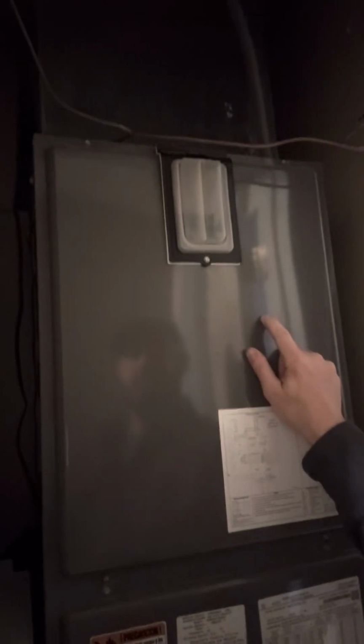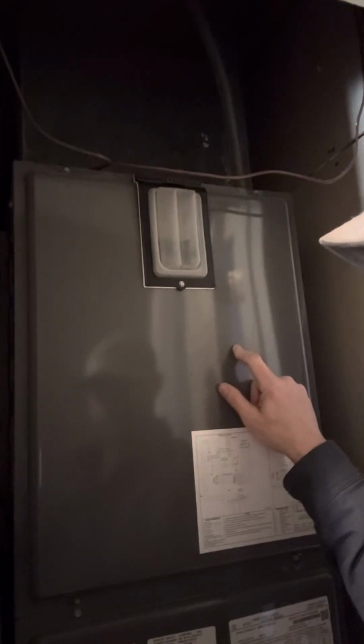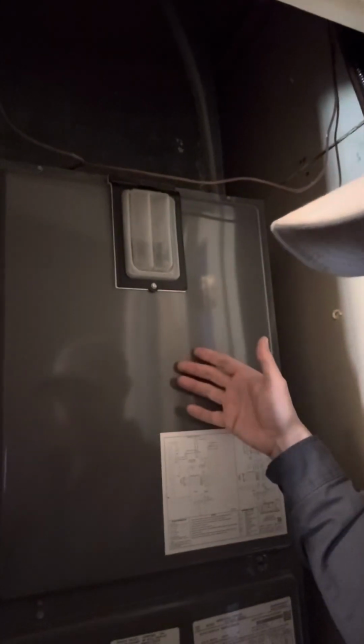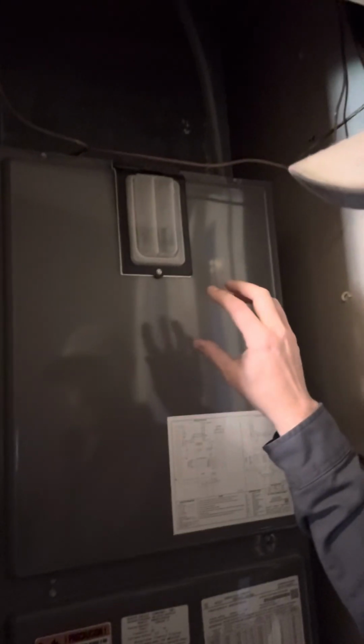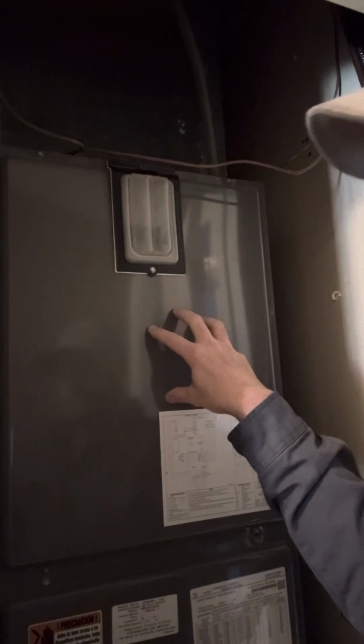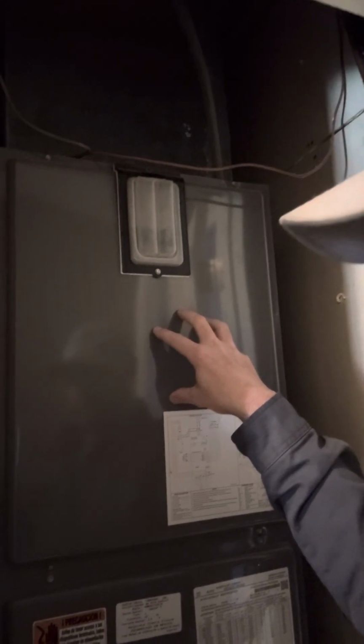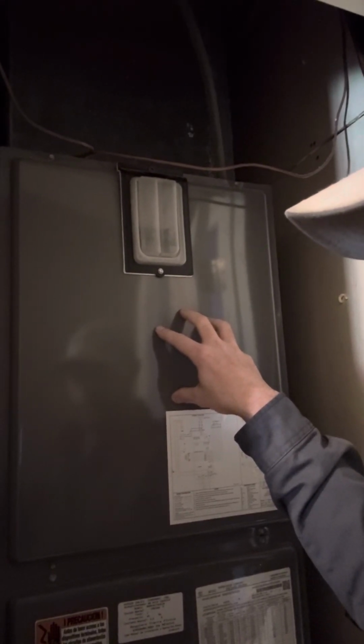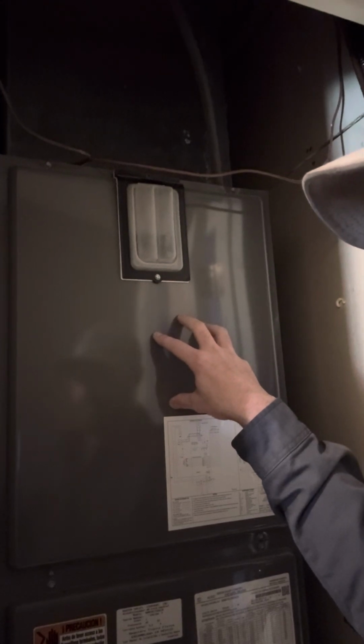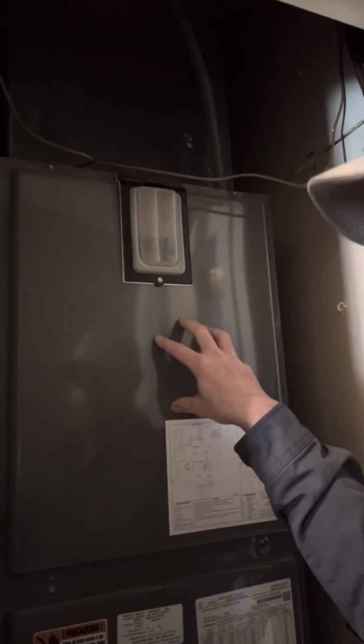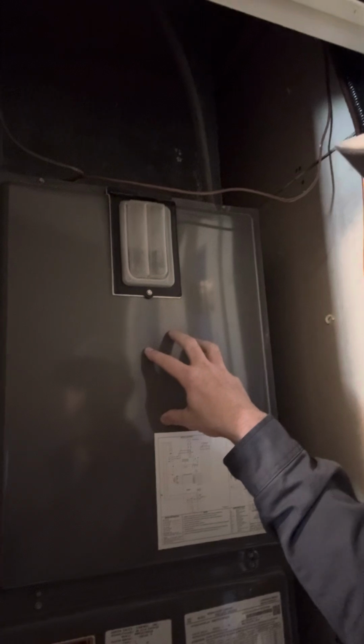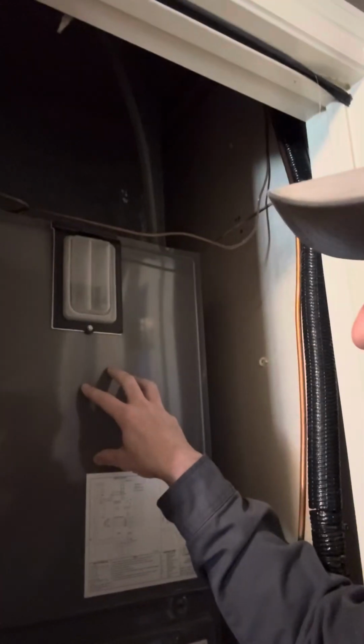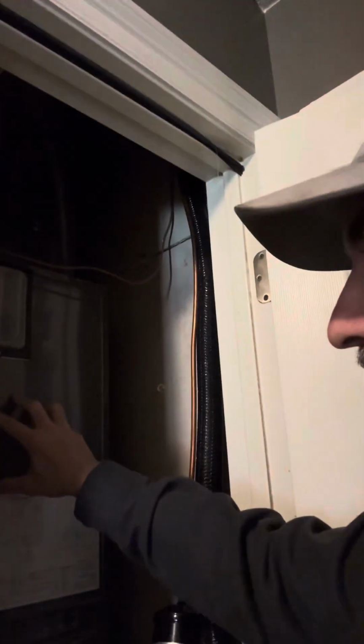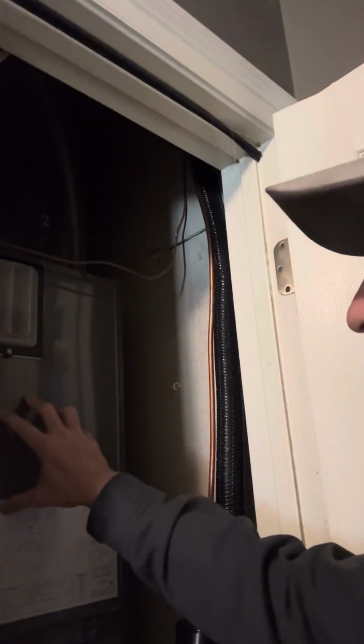if you don't have power at your thermostat, again, check your fuse. So it could be a low voltage issue. I'd always check the fuse. If your fuse is blown, I would check outdoors, check all your low voltage components. I've seen a lot of times a dog will chew the wires or something like that and blow the fuse. So you need to repair that before you move forward.